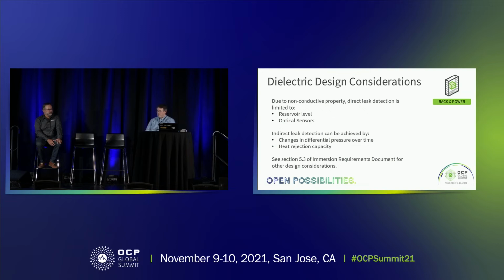So you're limited with a non-conductive medium, because you want your dielectric or your refrigerant to be non-conductive. You're looking at differential pressures, turbidity, level sensors in reservoirs and things like that to tell you if you have your cooling medium escaping your loop. We'll call it a closed loop system. So there can be a difference in differential pressure over time, and you have to have the algorithms or the logic in place to determine if nodes were taken out of the loop, and that's going to affect the differential pressure. Racks were added to the loop or turned off from the loop, and that changes the parallel pressure, and all those things, and monitoring that.